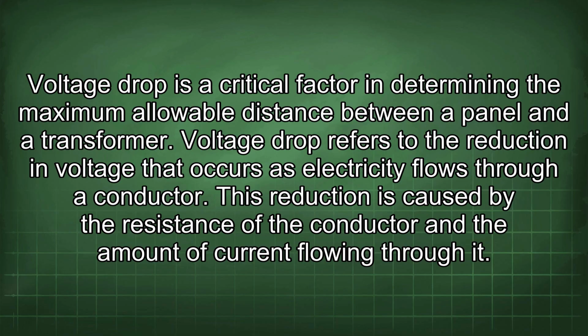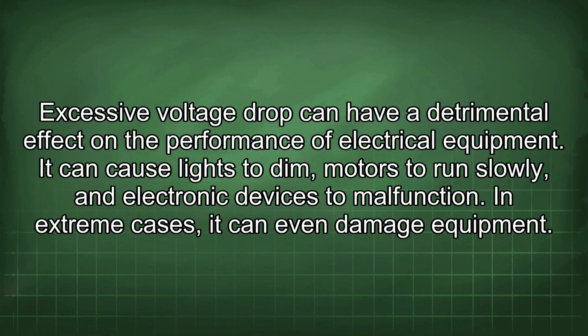Voltage drop is a critical factor in determining the maximum allowable distance between a panel and a transformer. Voltage drop refers to the reduction in voltage that occurs as electricity flows through a conductor. This reduction is caused by the resistance of the conductor and the amount of current flowing through it. Excessive voltage drop can have a detrimental effect on the performance of electrical equipment. It can cause lights to dim, motors to run slowly, and electronic devices to malfunction. In extreme cases, it can even damage equipment.